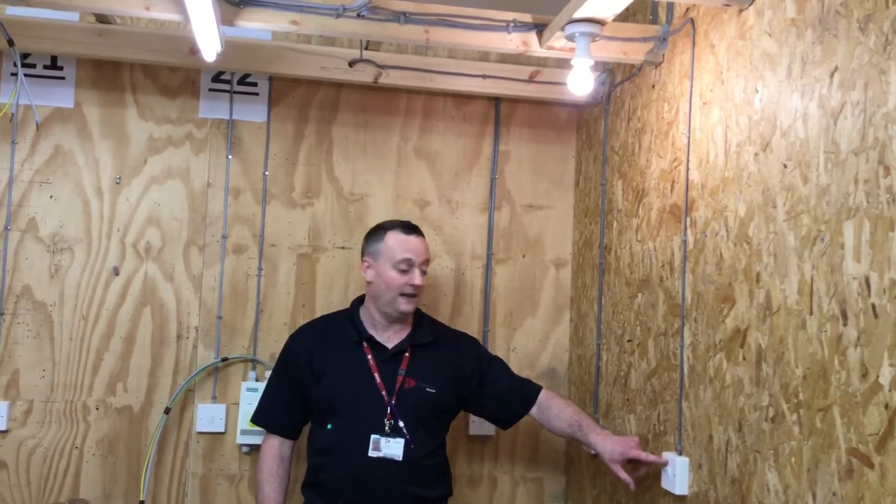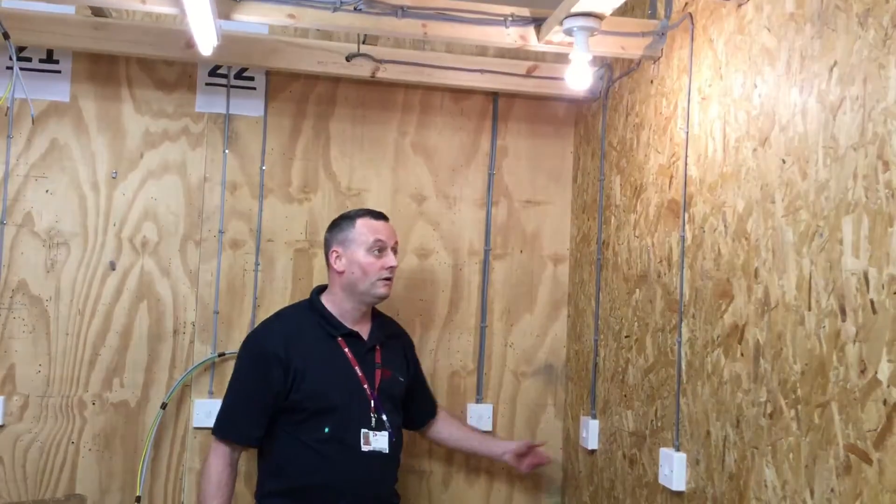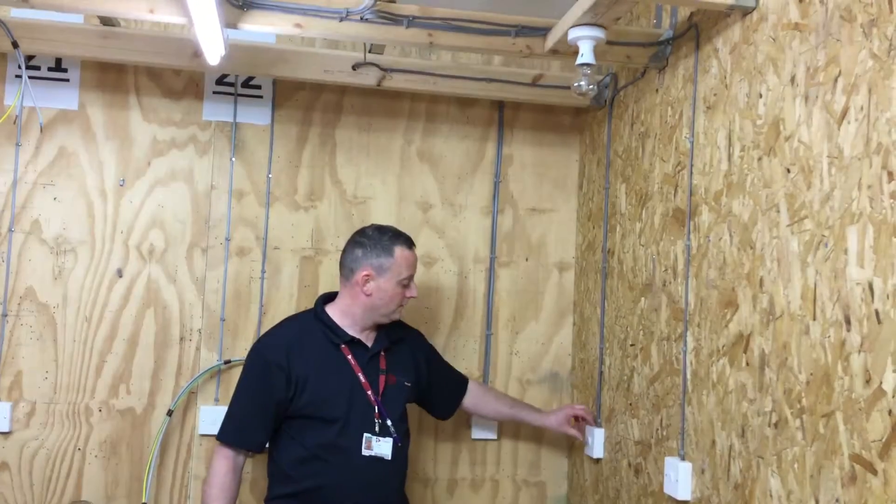Two-way switching and intermediates - now checking our batten lamp holder, so we should go off, on, to prove the functionality of the switches and polarity.